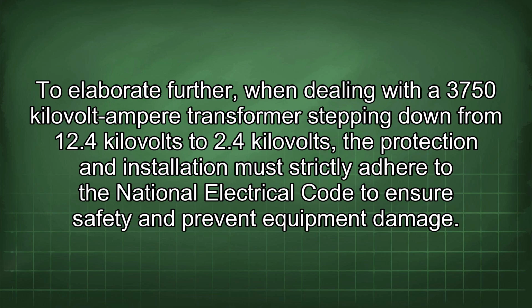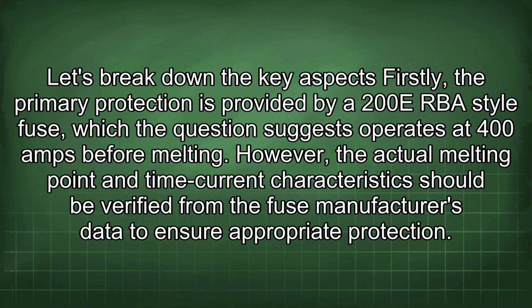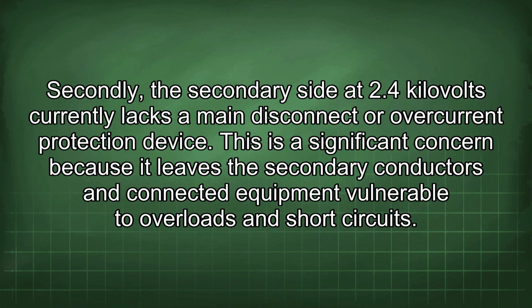To elaborate further, when dealing with a 3750 kVA transformer stepping down from 12.4 kV to 2.4 kV, the protection and installation must strictly adhere to the National Electrical Code to ensure safety and prevent equipment damage. Let's break down the key aspects. Firstly, the primary protection is provided by a 200E RBA style fuse, which the question suggests operates at 400 amps before melting. However, the actual melting point and time current characteristics should be verified from the fuse manufacturer's data to ensure appropriate protection.